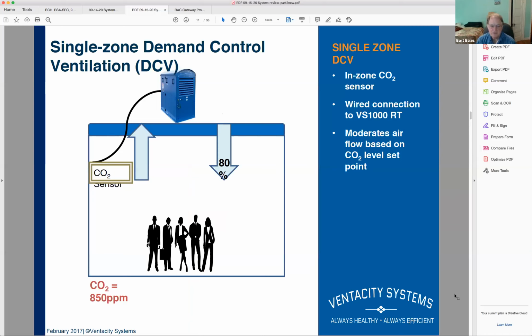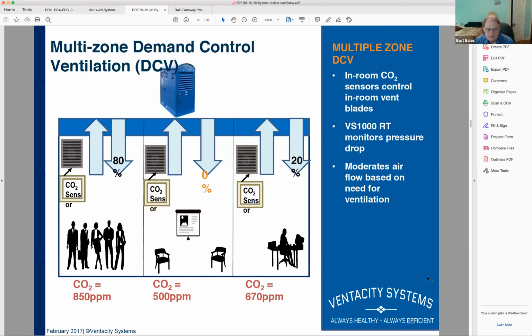So one of the things, if you're segregating the ventilation, you can demand control it. You can have a CO2 sensor that will allow you to estimate how many people are in the space, and by estimating how many people are in the space, you can dial up or dial down the amount of ventilation to match the amount that is required for that occupancy. And this can result in very significant savings because many spaces may be only occupied some of the time. Next slide. And you can do the same thing for a multi-zone system as long as you have sensors in each space. You can accomplish the same kind of effect. Next slide.